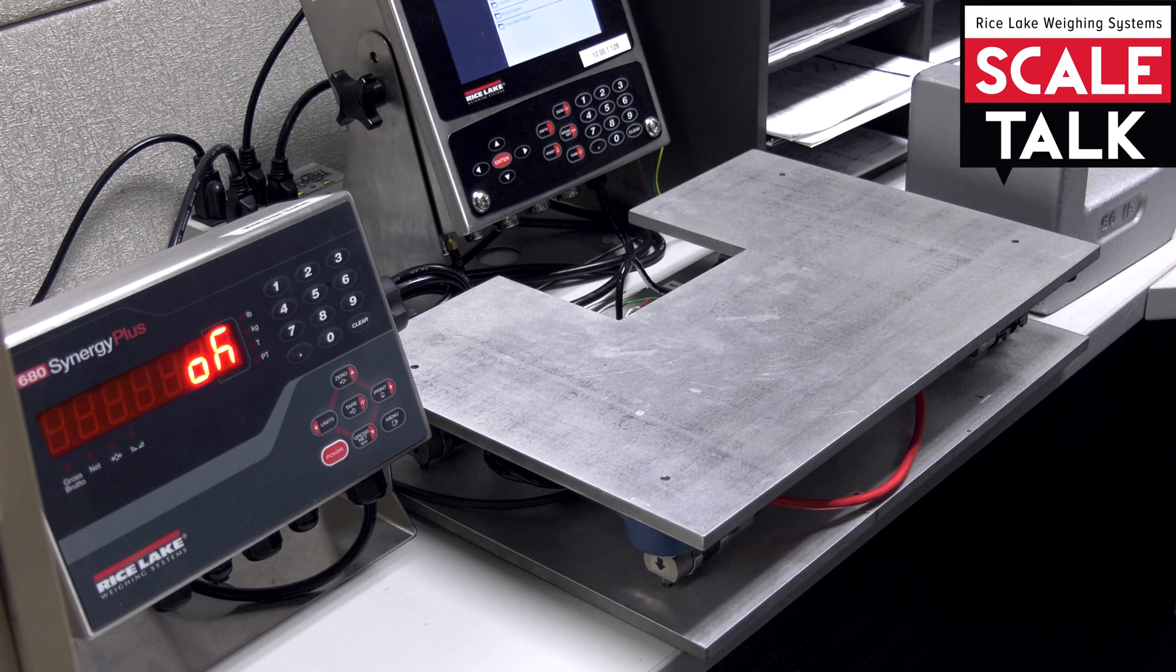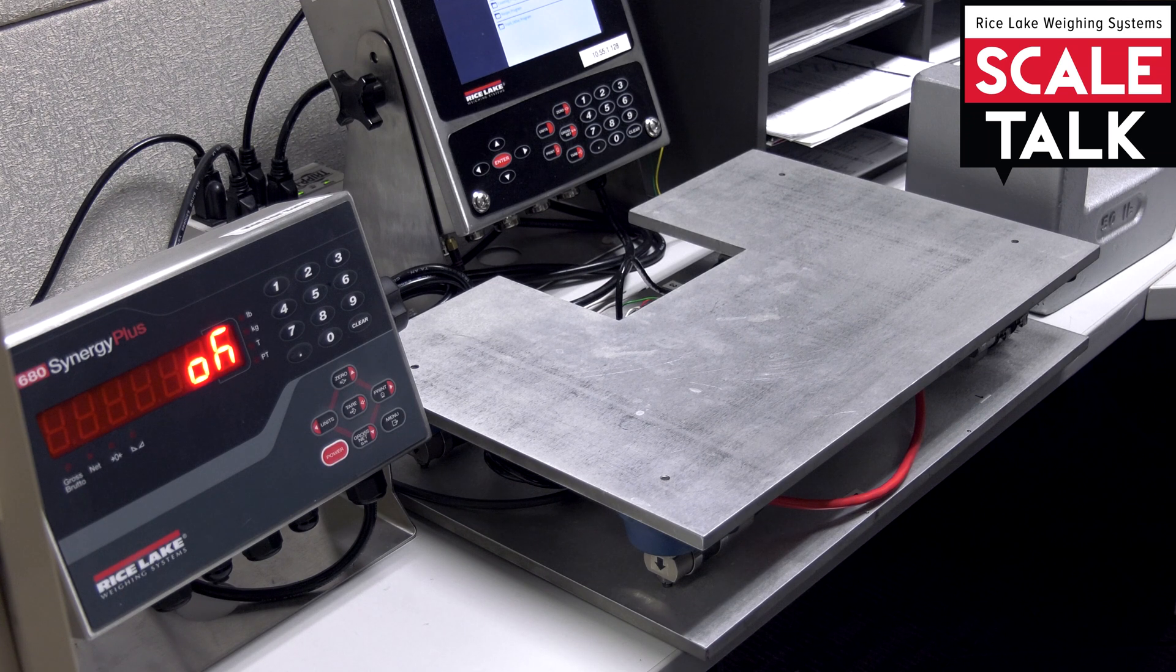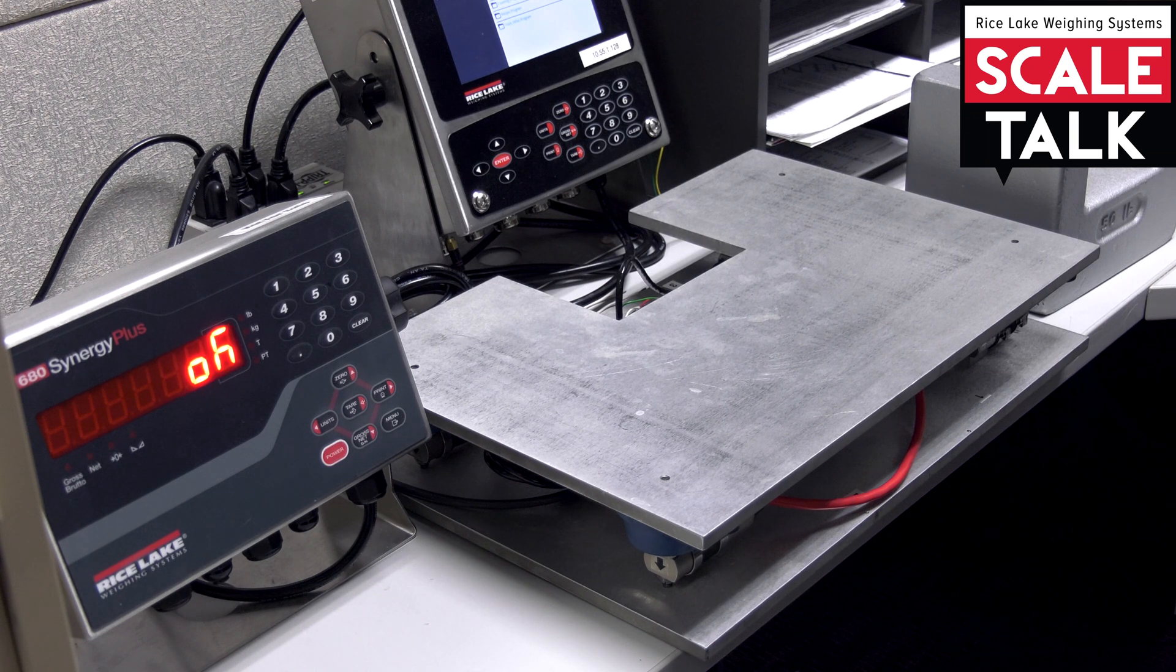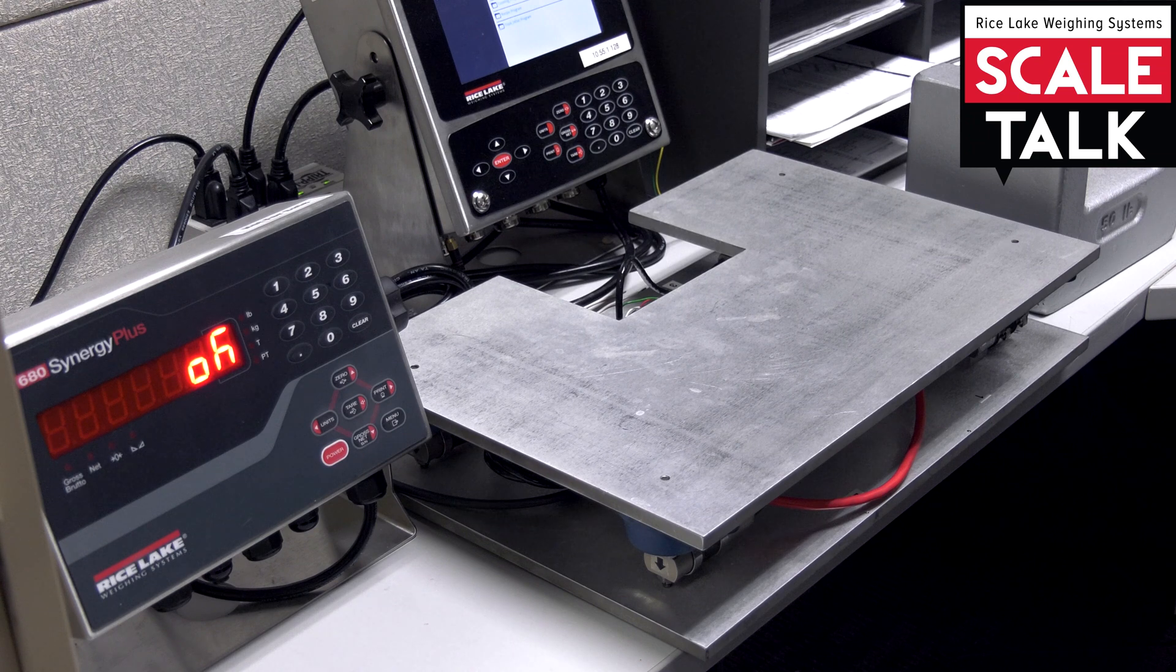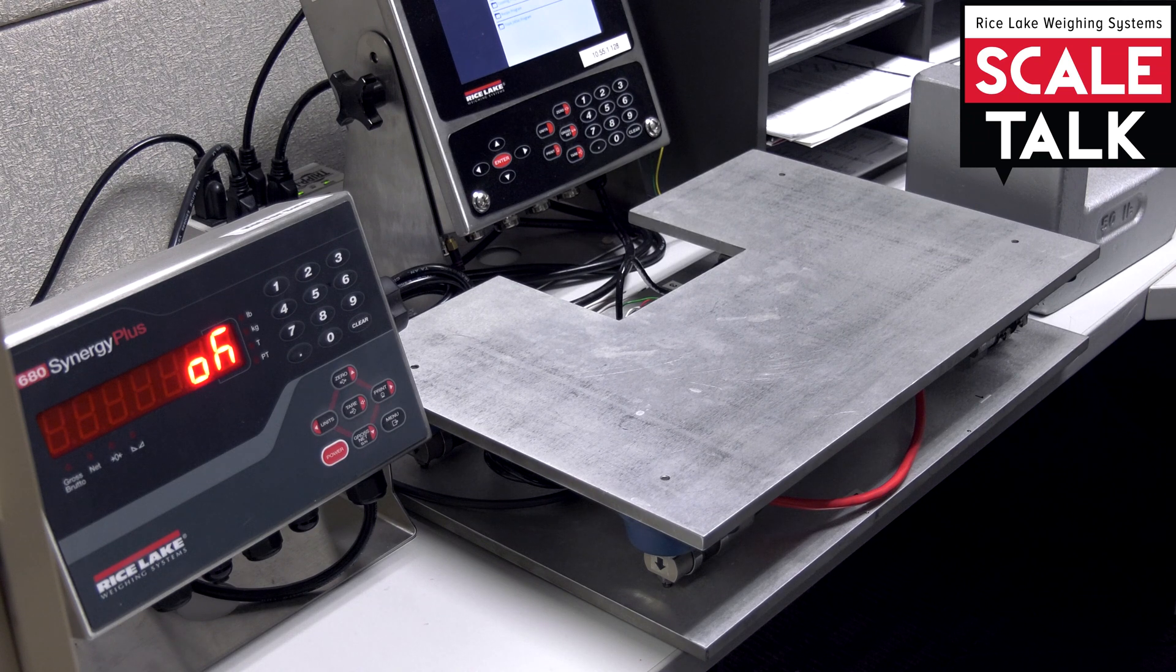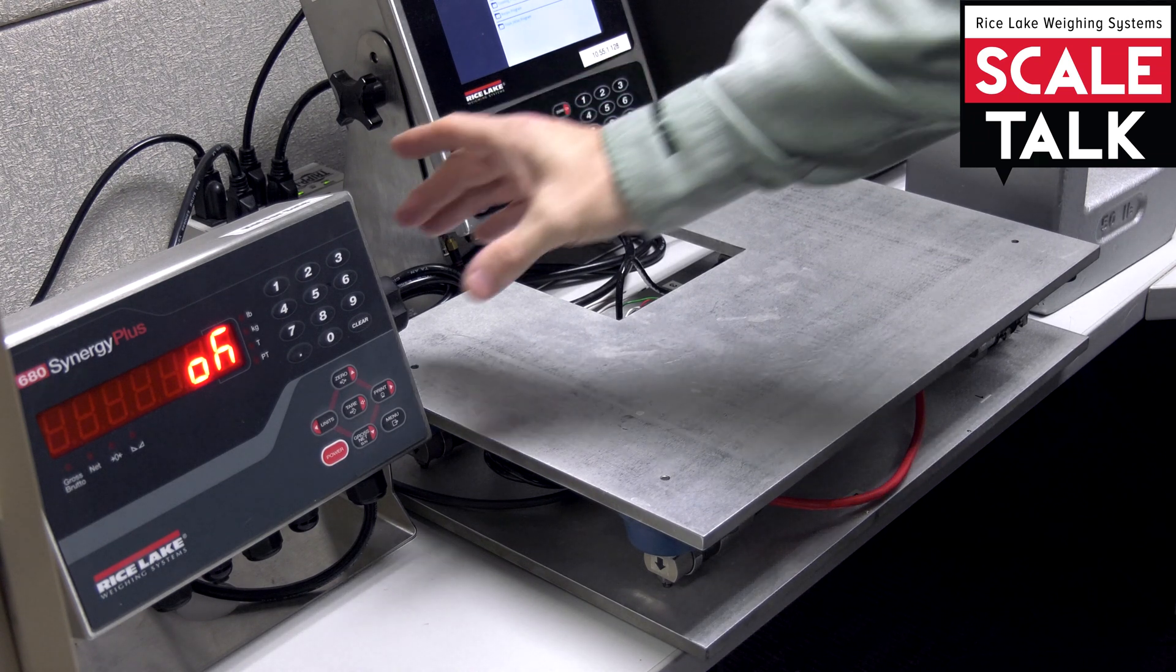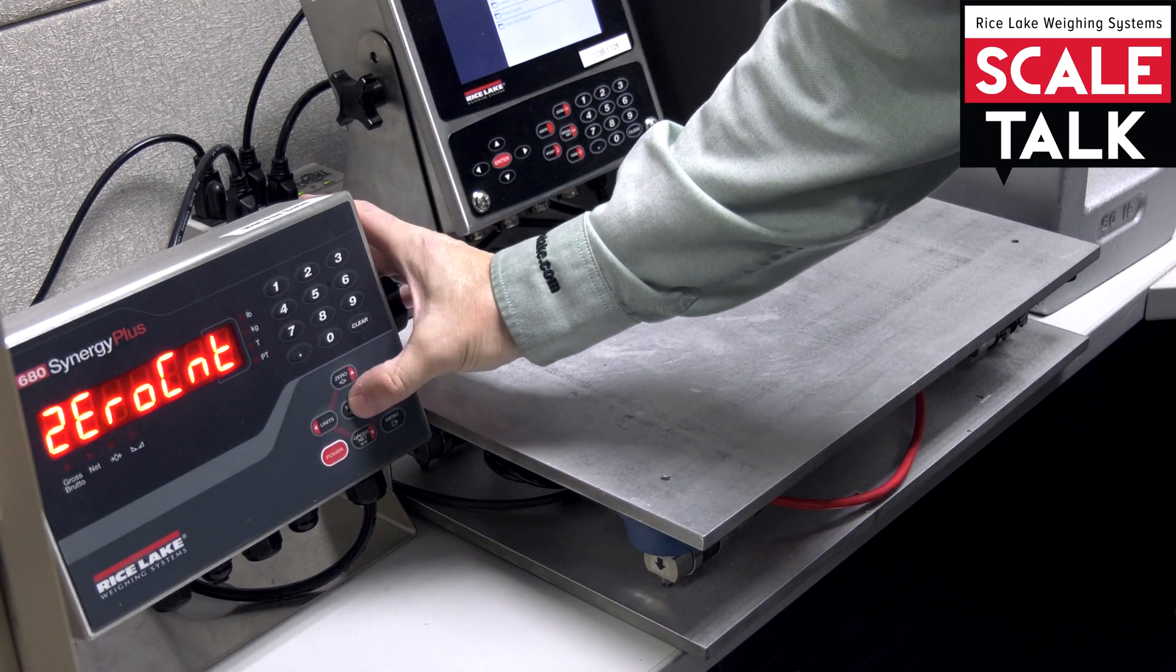Now that the zero calibration is complete, and it lets me know with the OK message here on this particular model, the 680, I'm going to go ahead and accept that value.